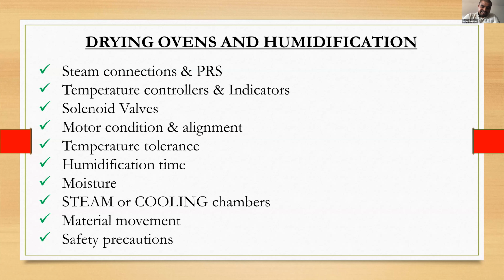Like we said for cooking, here too we have to use PRS for proper steam flow. The steam consumption is very less here for the ovens. Let me explain in technical terms: using these slides, there is a solenoid valve, and the steam line comes to the solenoid valve, which connects to the temperature controller that we have to adjust.